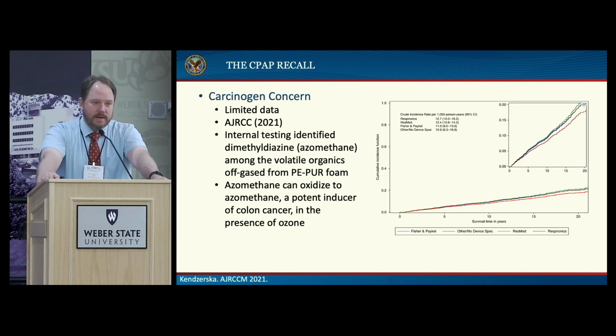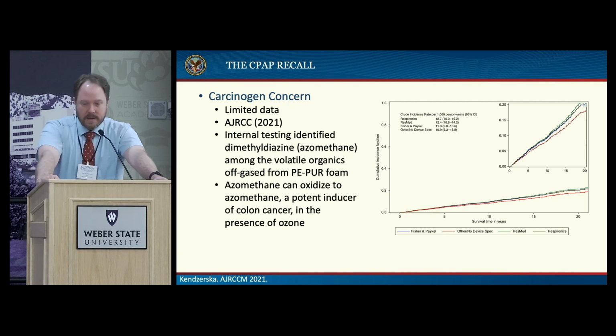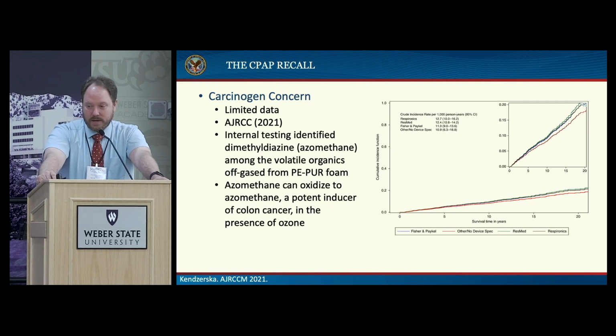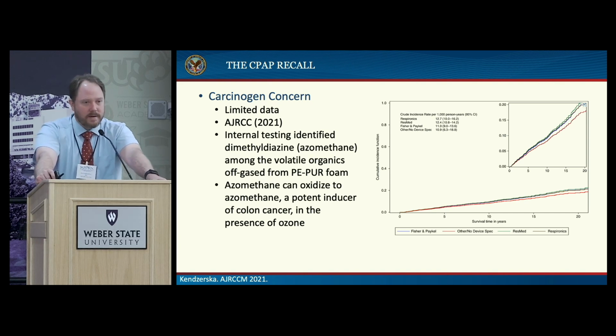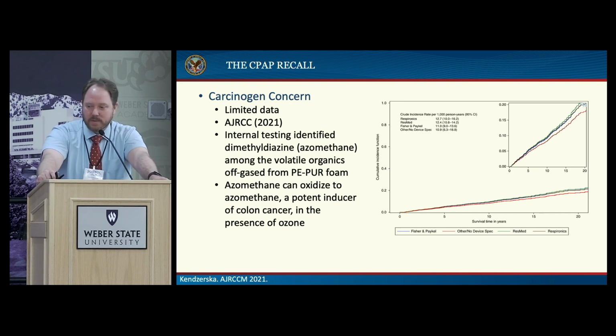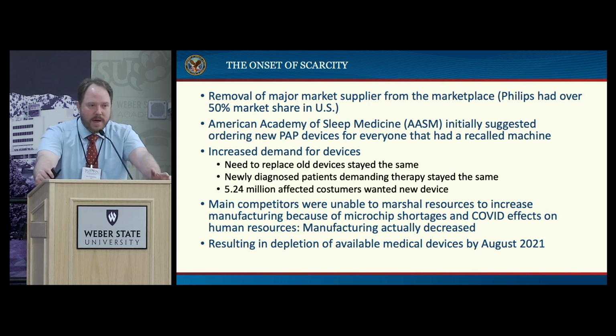But in the internal testing that was done by the manufacturer, they did identify an off-gassed volatile organic compound, dimethyldiazine, which is another word for azomethane. And azomethane can be oxidized into azoxymethane, which is a potent inducer of colon cancer. And so the concern was that if these machines had the foam degrading and that foam was getting into the air channel and was exposed to other oxidizing agents such as third-party sanitation devices which use ozone or ultraviolet light, these could produce carcinogens that patients would be inhaling. So that occurred in June.